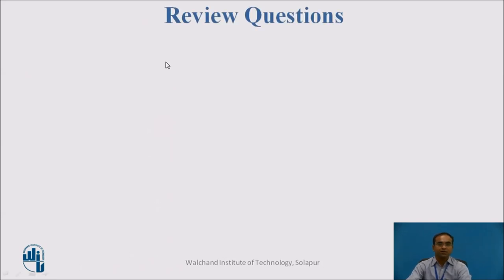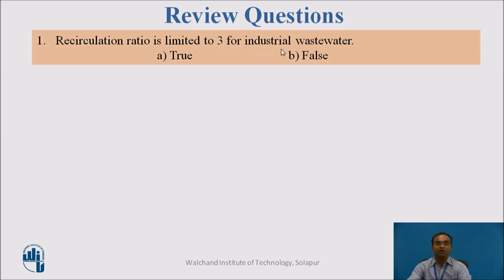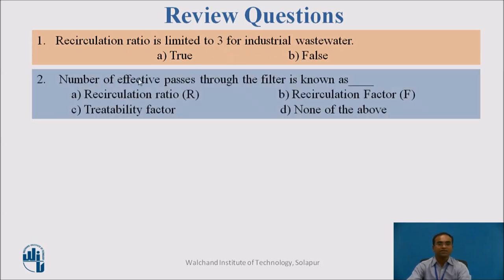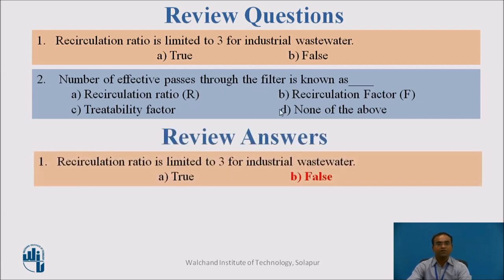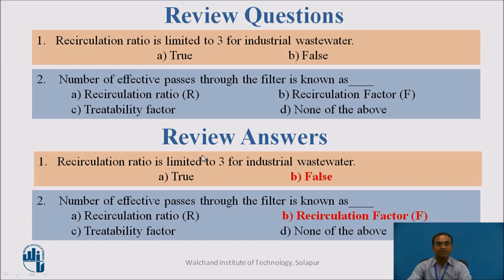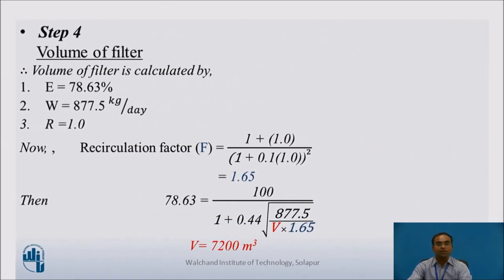Review question: The recirculation ratio is limited to 3 for industrial wastewater — true or false? The number of effective passes through the filter is known as the recirculation factor. Applying R = 1.0, the recirculation factor F = 1.65. Substituting F into the NRC formula gives the total volume = 7,200 cubic meters.